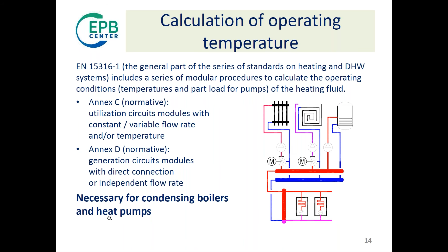And just to have a very simple example, maybe you know this typical schematic to control coils in the air handling units. You have a three-way valve and you are deviating the flow when you require less heat from the coil. What's the result? Typically, you run a constant flow rate, and here you're mixing hot water with the cold water from the coil, and you have warm water on the return as well.